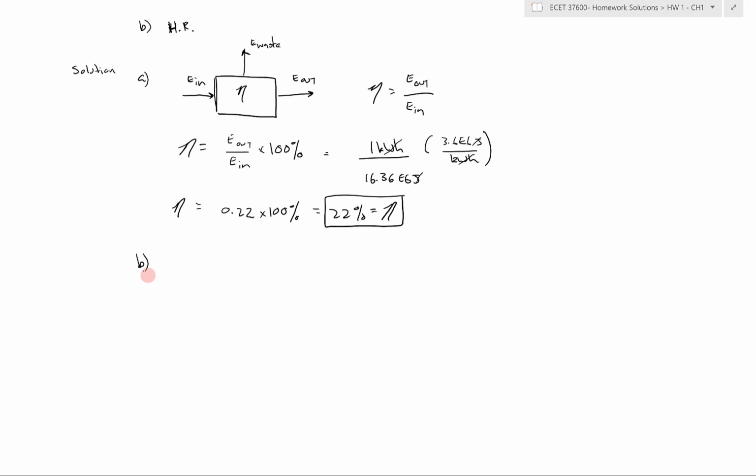But the formula for heat rate is, if the system was perfectly capable of, or 100% efficient at conversion, we know that there are 3,412 BTUs per kWh. That's just the heat content of a kWh, or just think of it as a conversion unit. 3,412 BTUs in a kilowatt hour, or 1 kilowatt hour is equal to 3,412 BTUs. It's just a conversion efficiency, right?